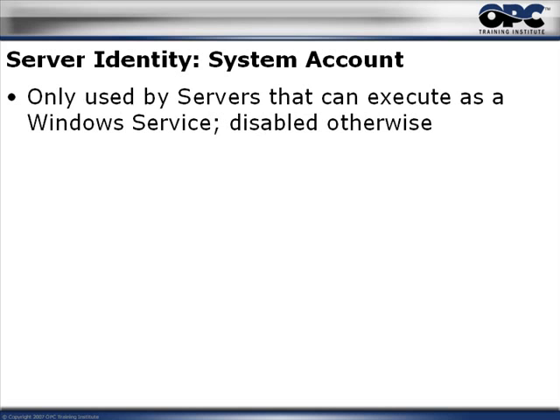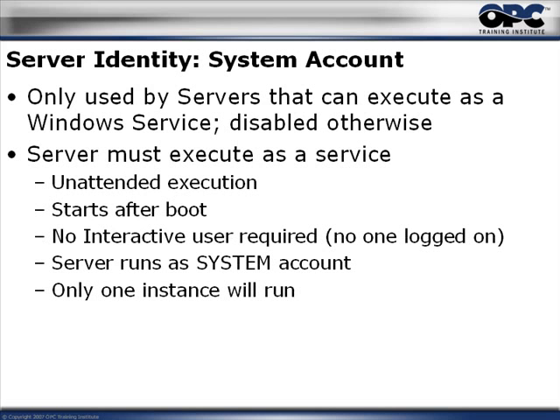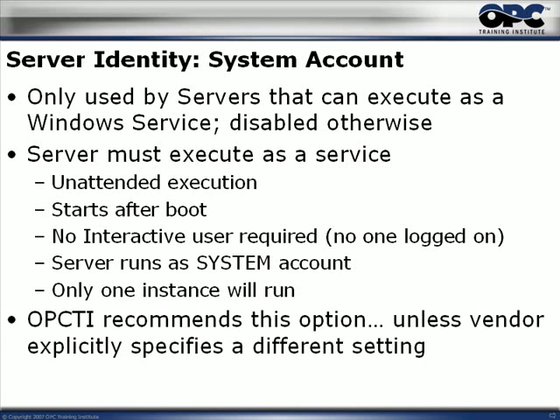The system account can only be used by OPC servers that execute as a Windows service. If a server isn't set up as a Windows service, that option will be disabled in the dialog box. The server runs completely unattended — nobody needs to be logged in — so it can start immediately after a reboot. It runs as a system account recognized by every application, and there is only one instance. This is what we recommend: unless your vendor tells you otherwise, use the system account server identity.